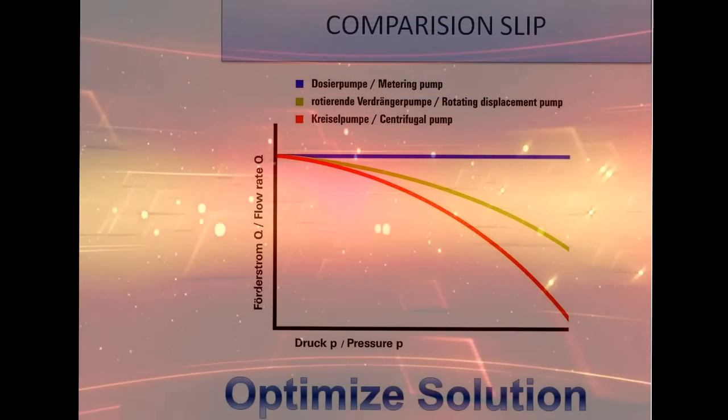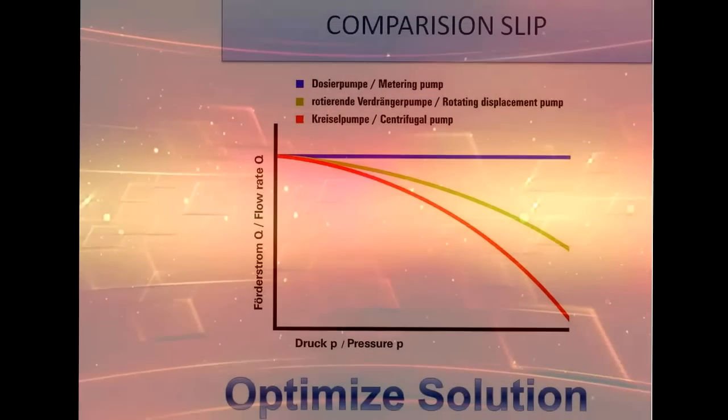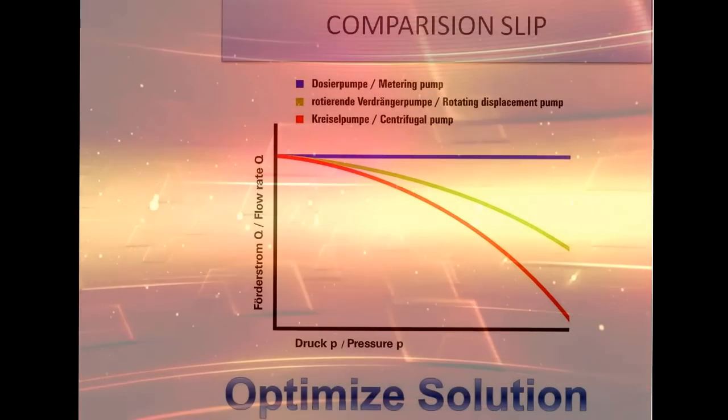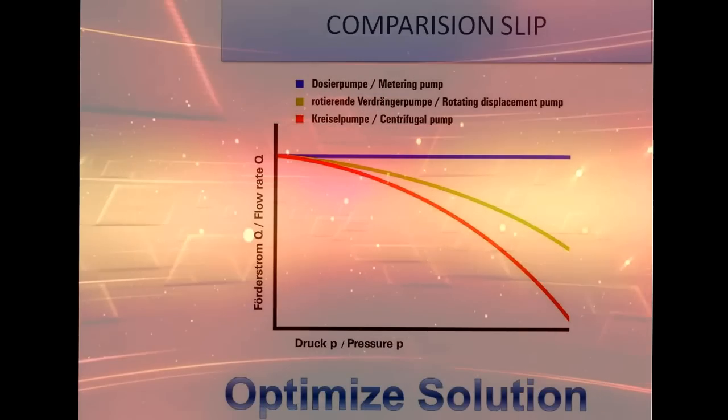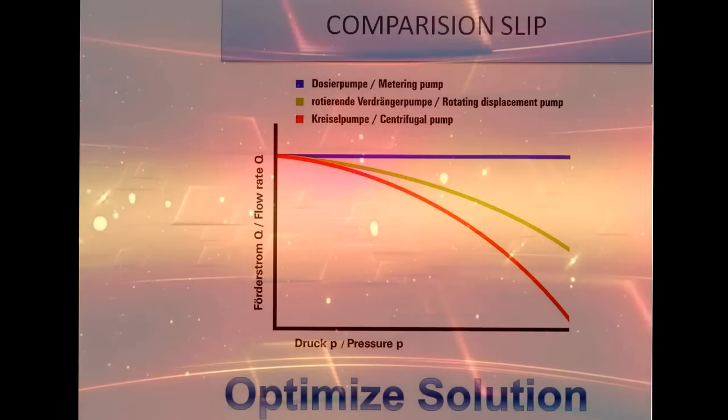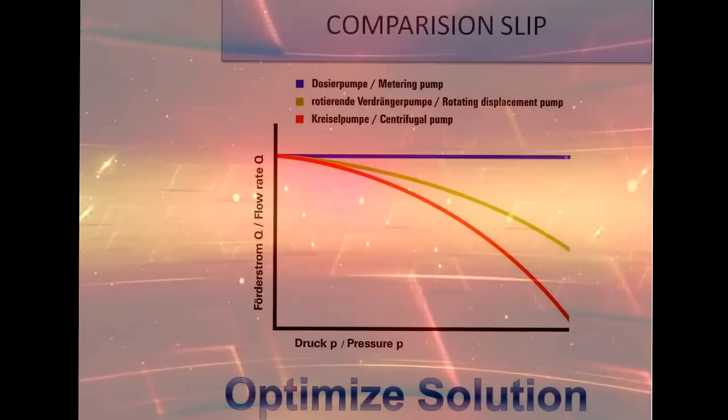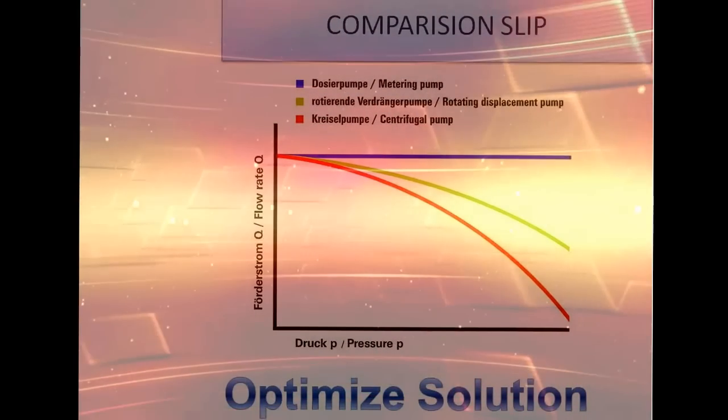This movement of liquid is called slip. The more the differential pressure, the more is the slip — that is the tendency of liquid in a rotary pump to move towards the suction side.